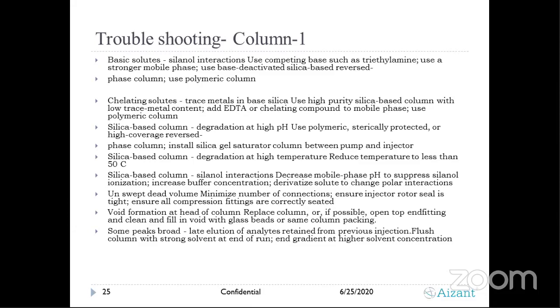So before taking a call that the column is not working, I suggest everyone relook at the 4 previous components: the mobile phase, which we have discussed, the injector system, the pump system, and the detector. Then we should close, and the last to look at will be your column. I'm reversing the whole order in which people first start with the column and then go to the other components. So always look at the first 4 other components and then come to the column. So why will the column pose a lot of challenges during your routine analysis?